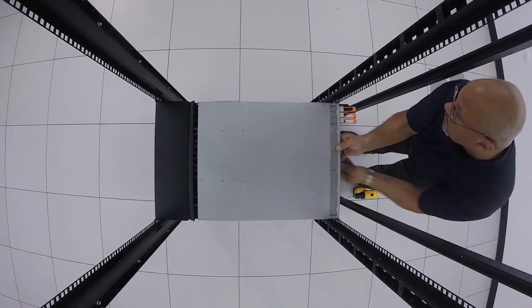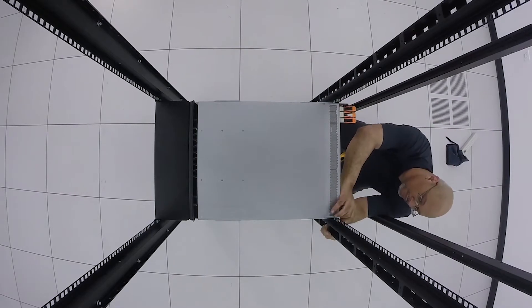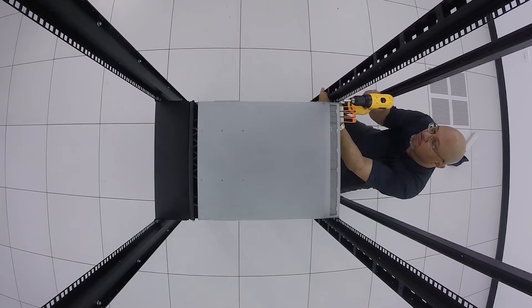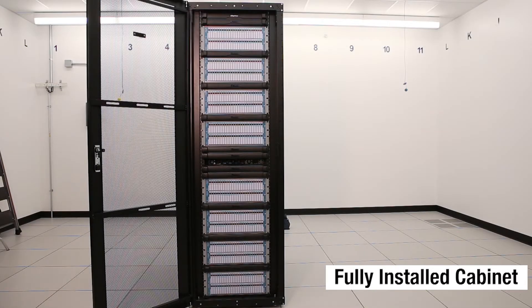Once the slide is in position, lock the slide in place with the fastener. Installing the switch using the thermal duct supports the back of the switch. A pass-through brush allows power to be supplied to the switch while maintaining maximum thermal efficiency.